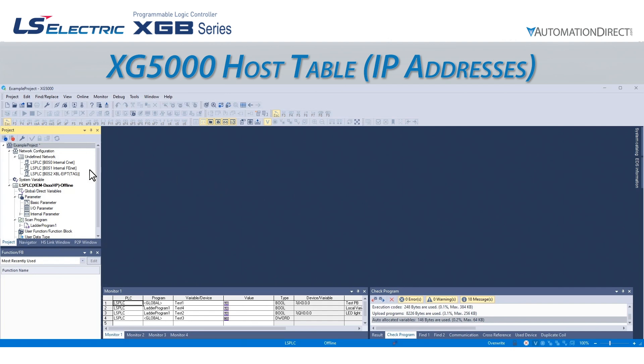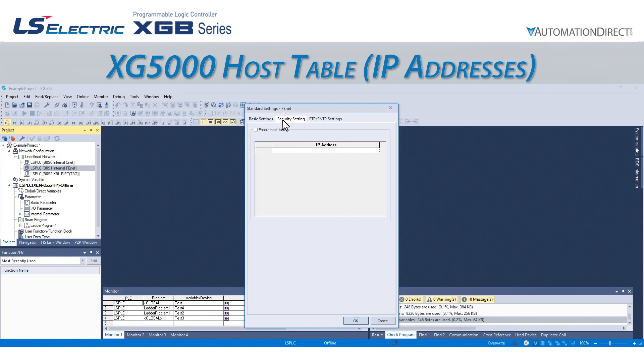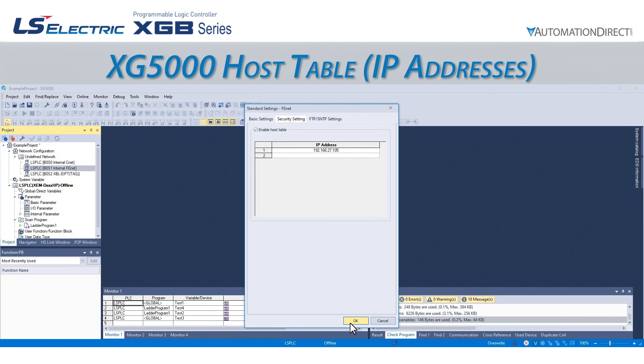To do this, we double-click on the internal FENet network. This will open the standard settings screen for this interface. We can go to the Security Settings tab and check the box for Enable Host Table. We can then enter the IP address of any device we want to allow a connection for. Up to 16 IP addresses can be registered in each host table. Let's add the IP address of a GS20 variable frequency drive we have connected.